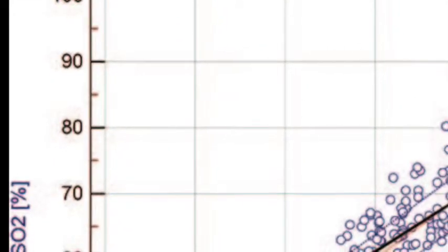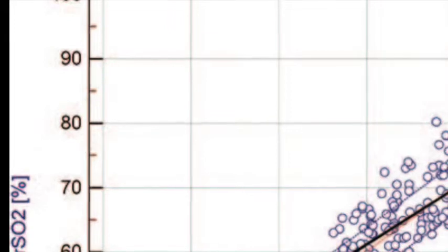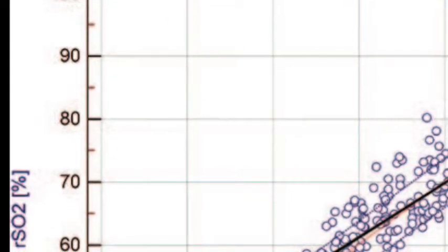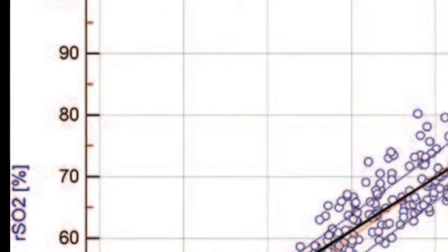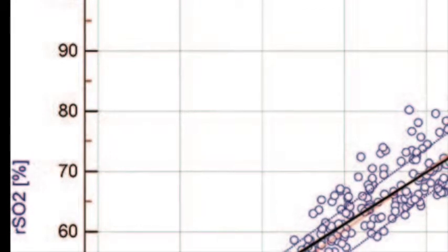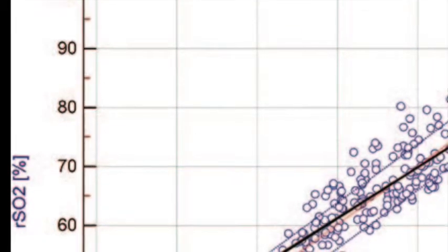They tested the monitor in 23 volunteers, 27 originally, though four dropped due to exclusion criteria, who breathed oxygen in different concentrations to achieve arterial oxygen saturation plateaus between 100% and 70%.